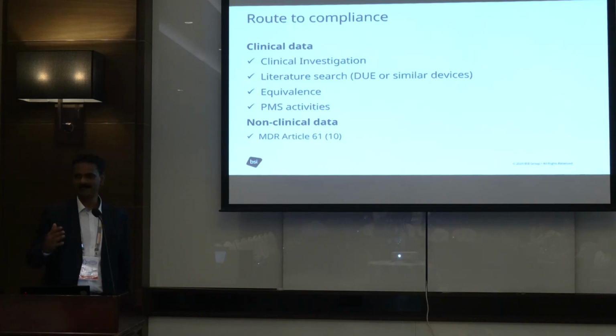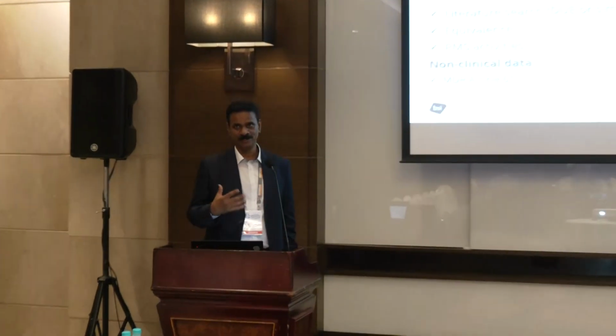When you write your CEP, clinical evaluation plan, or your clinical evaluation report, you need to make sure what route to compliance you are going to take. The route includes clinical data. Of course, you need sufficient clinical data to demonstrate compliance to MDR requirements. It could be clinical data obtained through clinical investigation or literature search.